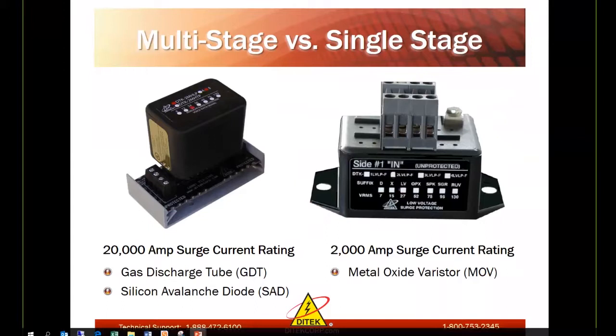On a single stage, it's our older legacy product, the LVLP series, which we still do offer at a lesser cost. It's a 2,000 amp surge current rating utilizing metal oxide varistors, or MOVs. We do offer it in multiple pairings. As you can see, that one there for the fire SLC would be the F series.